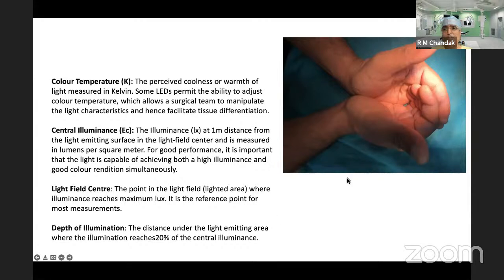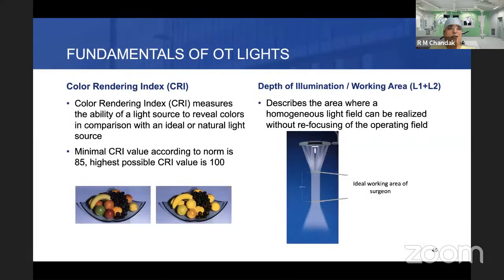The depth of illumination, you can simply look at the light beam and see the depth of illumination that we require in spine surgery or in deep surgeries. The color rendering index is also very important, and the modern LED lights give us this very nicely. The depth of illumination works best at around 1 meter distance, and this is the surgical field. So by and large, don't keep the light dome quite low down. It should be at 1 meter height so that we get this area for working, which is the parallel beam.